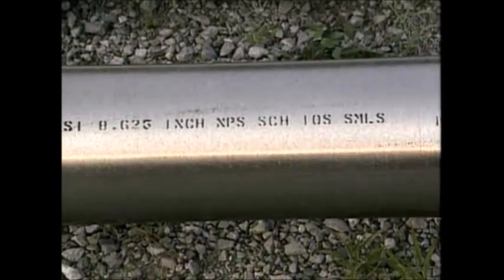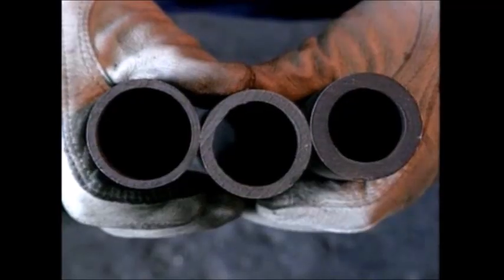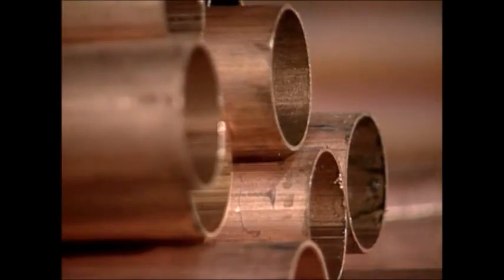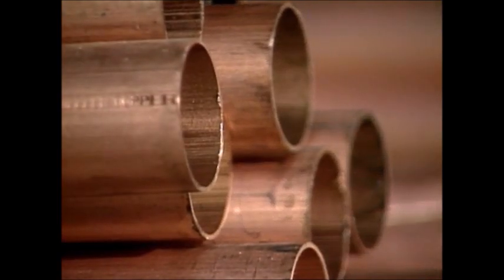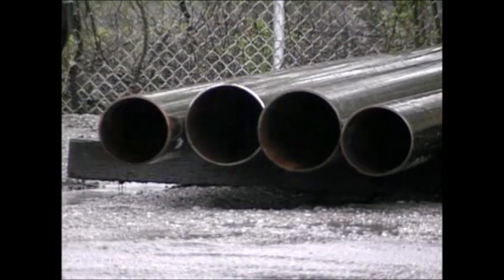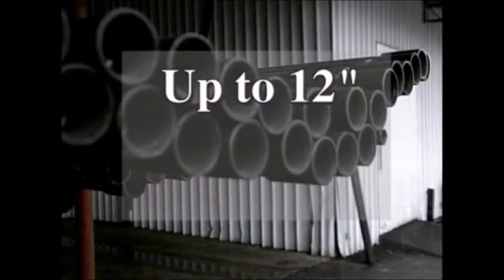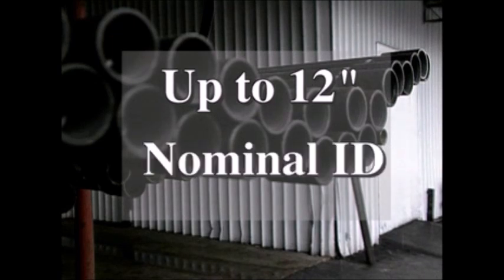This part will explain how pipe size is measured, what is meant by pipe schedule, and identify common piping materials. Commercial piping is available in sizes from 1/8 inch to 48 inches in diameter, and specialized piping may be even larger. Up to 12 inches, the nominal pipe size, or NPS, refers to the nominal inside diameter, which differs slightly from the actual inside diameter, or ID.